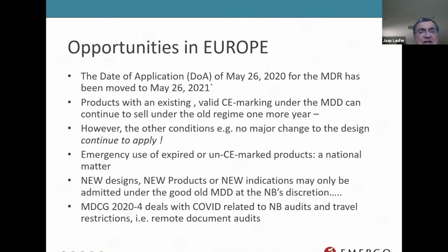Products with an existing valid CE marking under the MDD can continue to sell under the regime for one more year, but you have to talk, as I've said before, to your notified body. The other conditions, no major change to the design, continue to apply, because then you lose that opportunity and come automatically under the MDR.